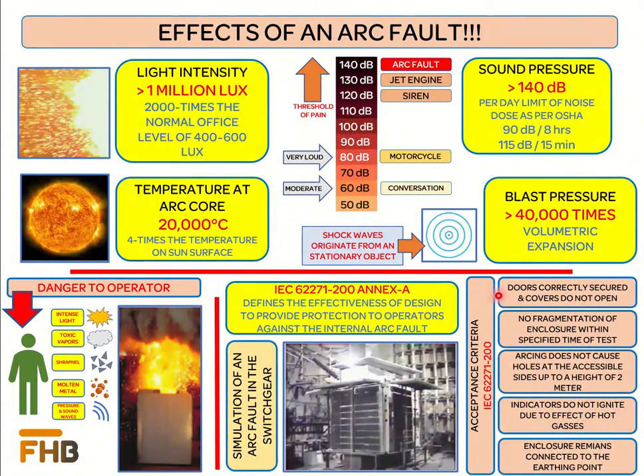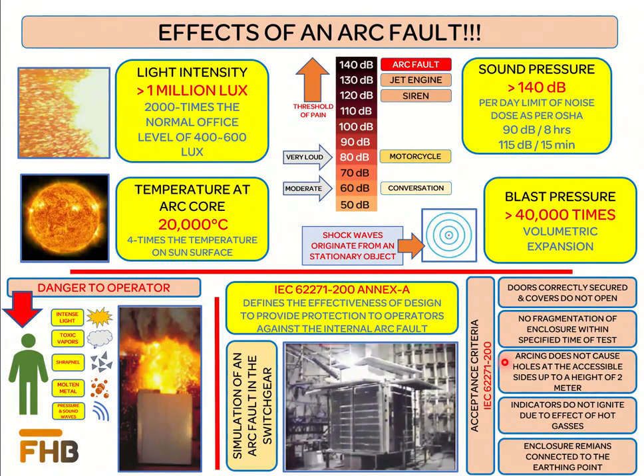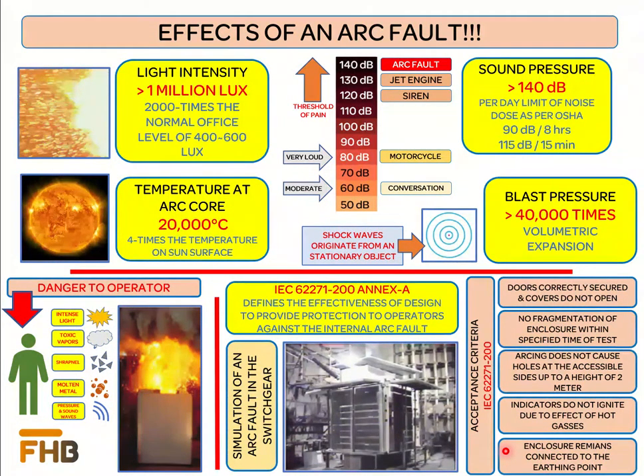For an enclosure to qualify as internal arc classified, the acceptance criteria as defined by IEC 62271-200 must be met after the initiation of an arc fault within the switchgear assembly. First, after the test all doors should remain closed and covers must not open. Second, there should be no fragmentation of the enclosure during the specified test duration. Third, arcing must not cause holes in accessible sides of the switchgear up to a height of 2 meters. Fourth, indicators — pieces of cotton cloth placed at designated locations to simulate burning due to hot gas emission — must not ignite. Fifth, the enclosure must remain connected to its earthing point. All these acceptance criteria are focused on the safety of operators working in the vicinity of the installation.